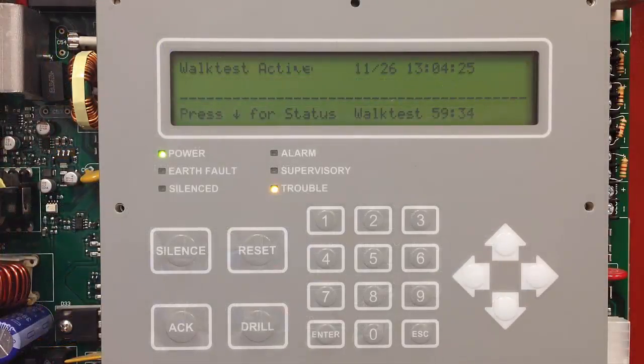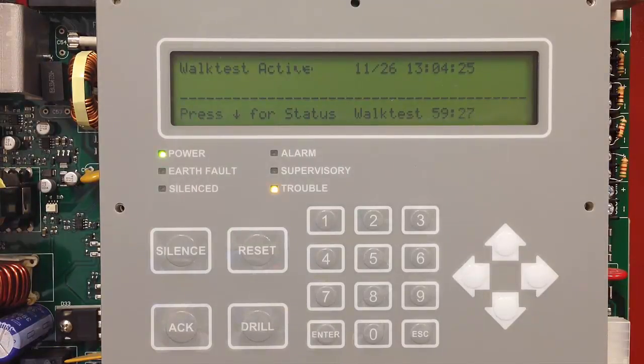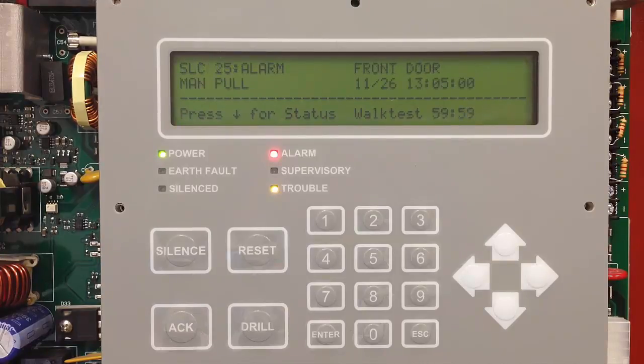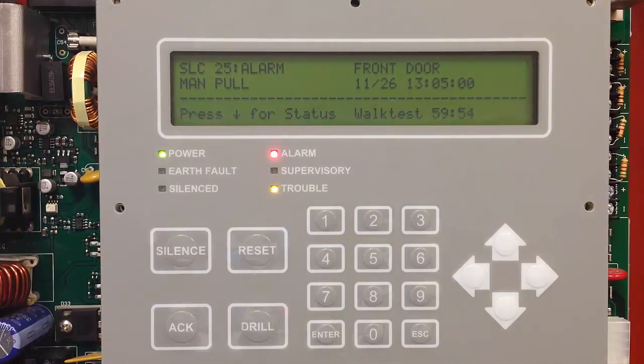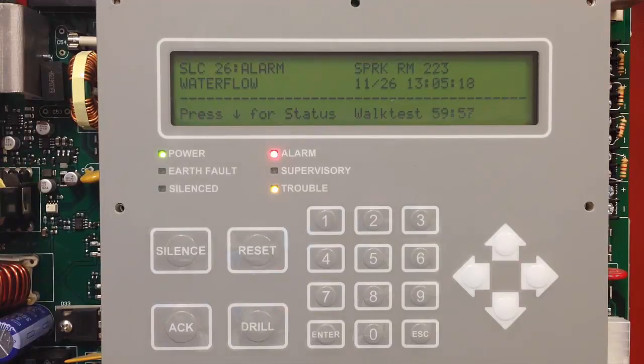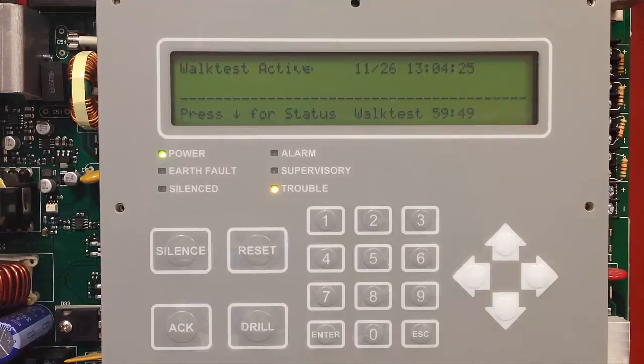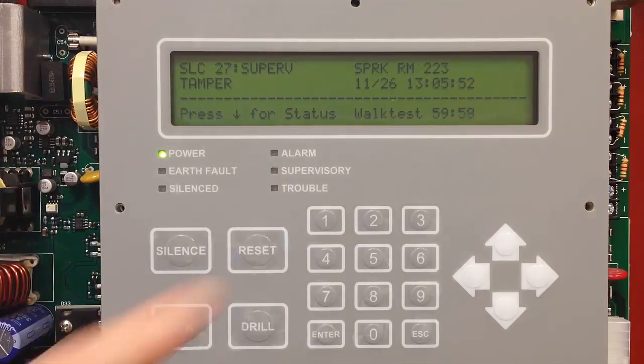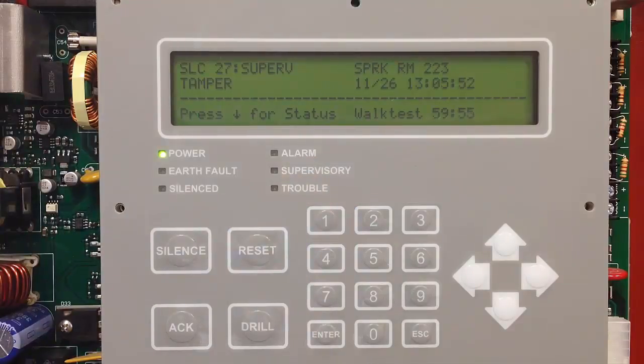At this point you can start testing devices in the field. Each time a device is triggered, it will show on the fire alarm control panel that the device is active and in alarm. Once the trigger clears in the field, the event will clear at the fire alarm control panel after a couple seconds. The LED of the device latches on when the device is tested and will stay latched on even when the device clears. Note that the SLC can power up to 13 LEDs when testing, so if you want to use the LED as an indication of test, you'll need to reset the walk test after testing 13 devices. The timer resets to 60 minutes each time a device is tested.